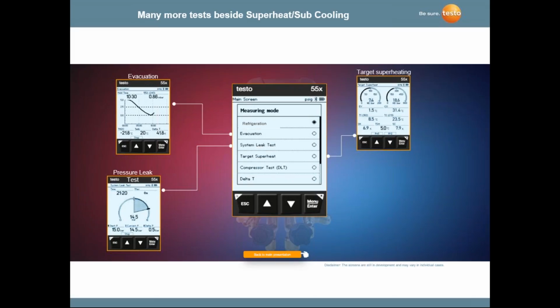Targeted superheat. We can do targeted superheat. We also have many smart probes, wireless probes, but one very common probe is our 605i, which is for relative humidity and temperature. And you use 2 of these probes simultaneously to get your targeted superheat. One would be outside near the condensing unit to get your outdoor dry bulb. The other is near your return air supply, where you're getting your wet bulb reading.